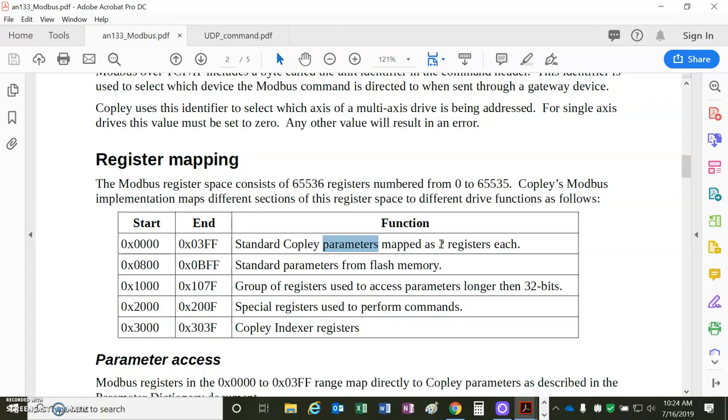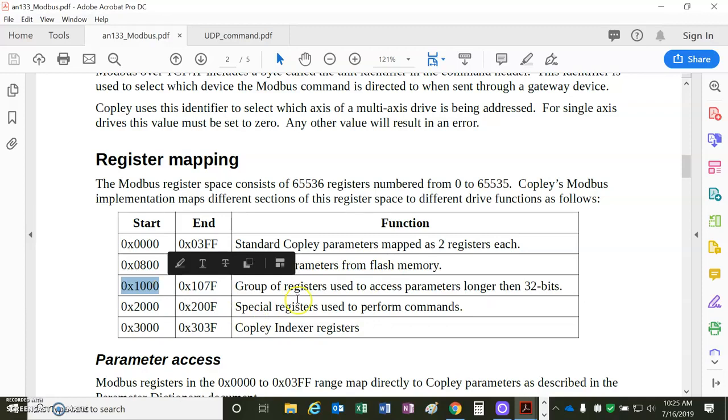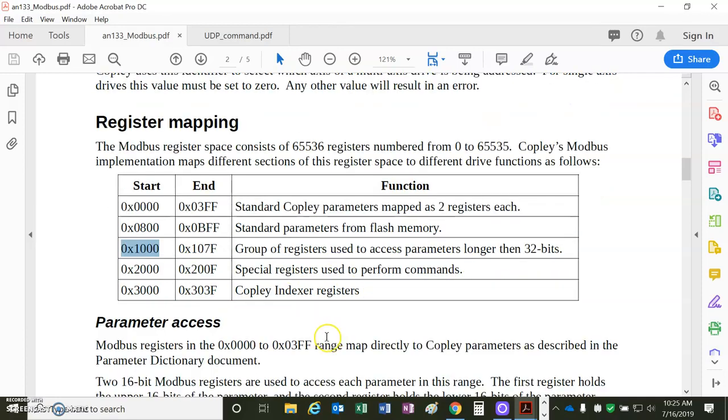We're going to use for read function code 3, and for write we'll use function code 16, which is 0x10. That's RAM, and 800 hex offset for reading flash, 1000 for the bigger parameters like the filters.